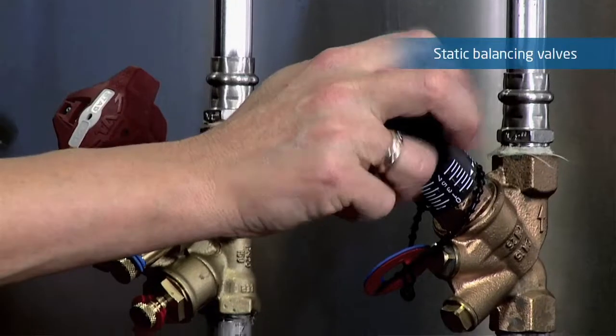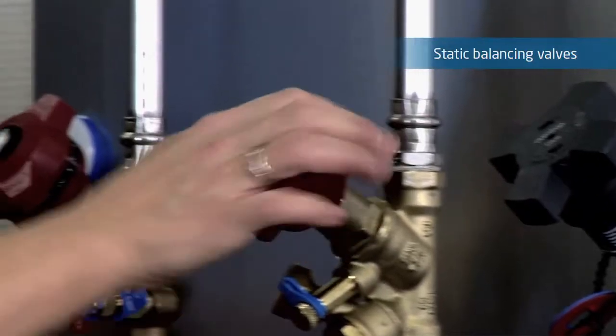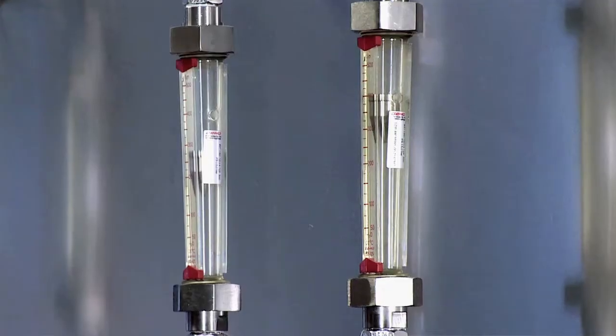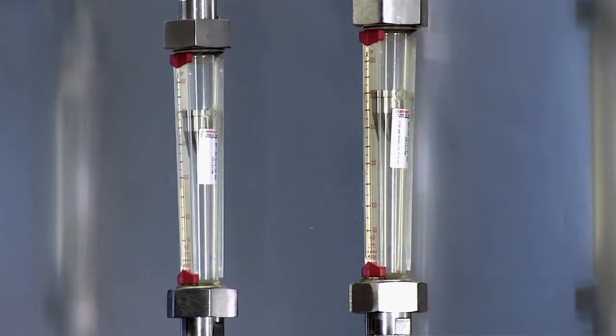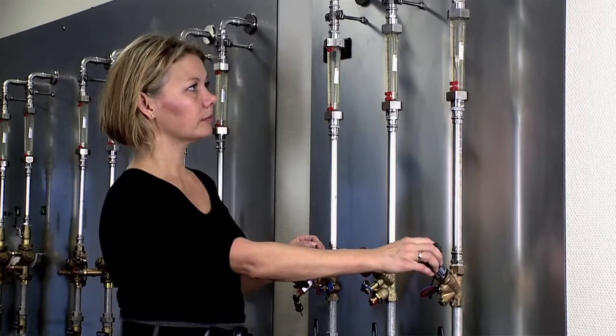One of the modern trends in heating and cooling systems is the use of inverter drives on pumps and what we call two-port control valves on things like fan coils and air handling units. These are fine, great devices which mean there's potential for the energy consumption of the pumps to be reduced when the system's not fully occupied or when you haven't got extremes of outside air temperature.